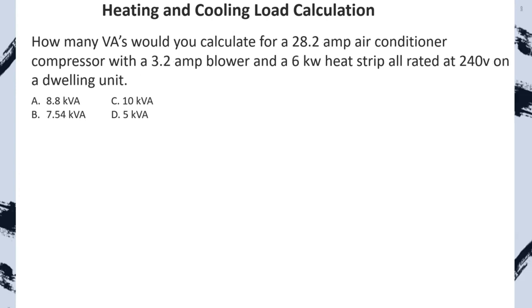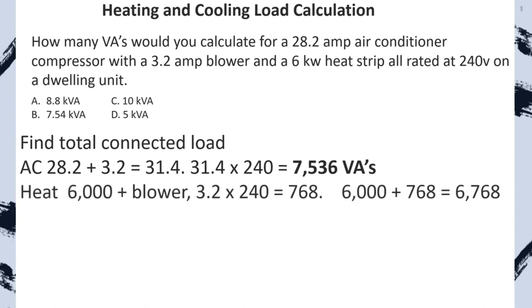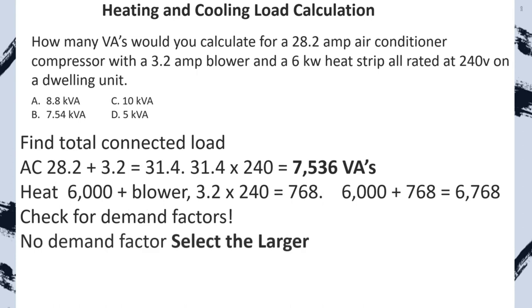Practice problem: How many VAs for a 28.2-amp air conditioner compressor with a 3.2-amp blower motor and a 6 KW heat strip, all rated 240V, on a dwelling unit? Total connected load for AC: 28.2 plus 3.2 equals 31.4 amps multiplied by 240V equals 7,536 VAs. For heat: 6,000 VA plus the blower motor (3.2 amps multiplied by 240V equals 768 VAs) totaling 6,768. Check for demand factors: none. Select the larger — the cooling at 7,536. Great job.